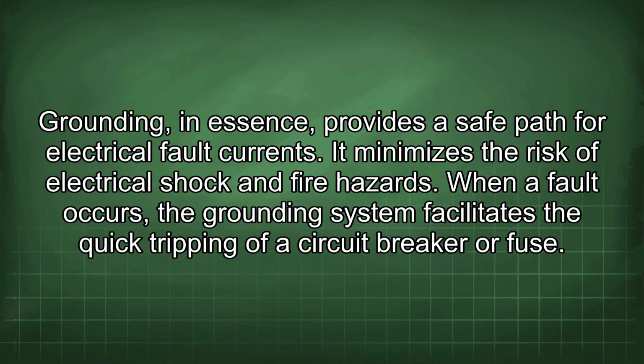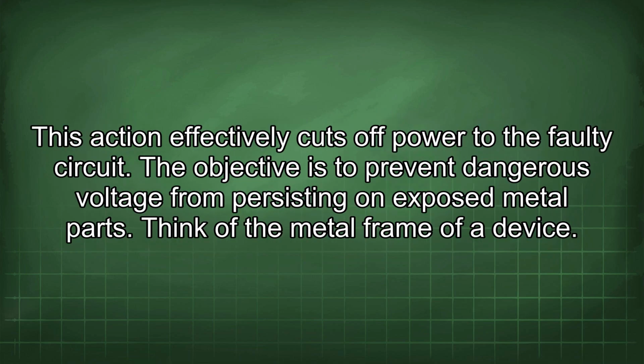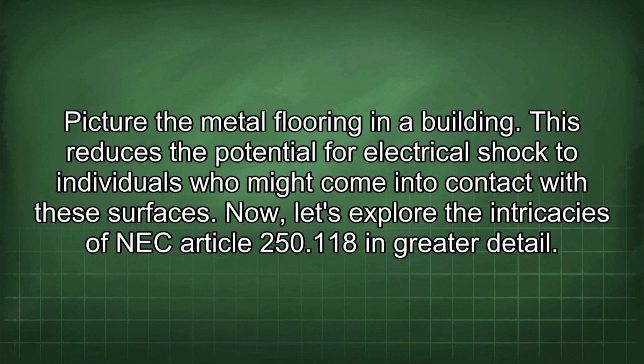Grounding, in essence, provides a safe path for electrical fault currents. It minimizes the risk of electrical shock and fire hazards. When a fault occurs, the grounding system facilitates the quick tripping of a circuit breaker or fuse. This action effectively cuts off power to the faulty circuit. The objective is to prevent dangerous voltage from persisting on exposed metal parts. Think of the metal frame of a device. Picture the metal flooring in a building. This reduces the potential for electrical shock to individuals who might come into contact with these surfaces.